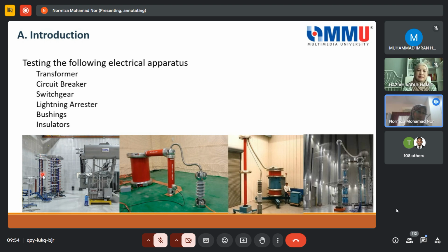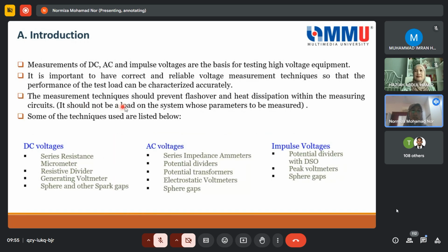So this capacitive divider, when connected to this impulse generator, the one that I pointed here, is when they are doing testing on the transformer, and it should not cause flashover. It means it should not be the source of flashover. If there is a flashover, it should likely come from the equipment, maybe some fault or flaw in the equipment, but not from this capacitive divider. So it should not be, in other words, part of the test load, because the test load here is your transformer.